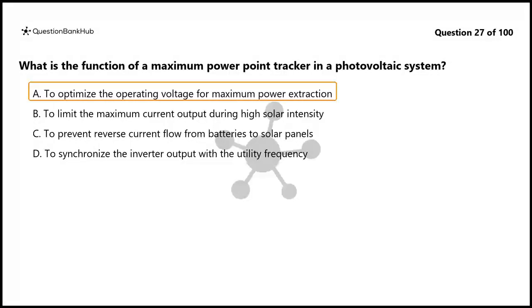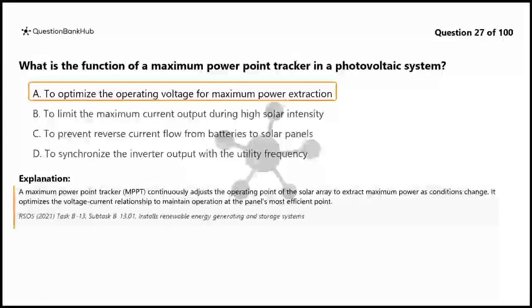The correct answer is A. To optimize the operating voltage for maximum power extraction. A maximum power point tracker, MPPT, continuously adjusts the operating point of the solar array to extract maximum power as conditions change. It optimizes the voltage-current relationship to maintain operation at the panel's most efficient point.